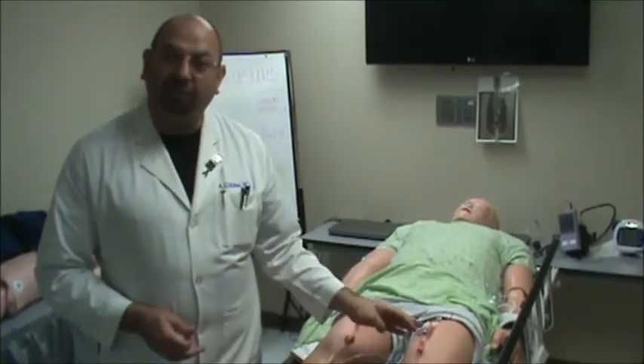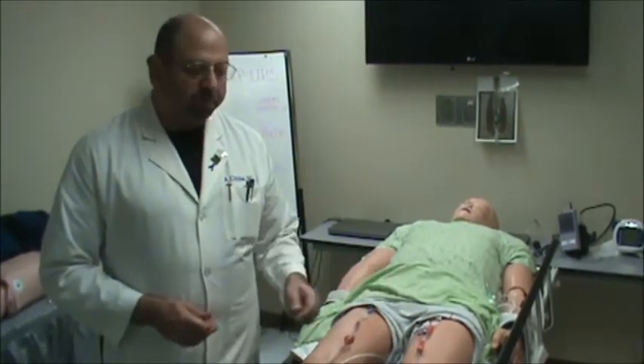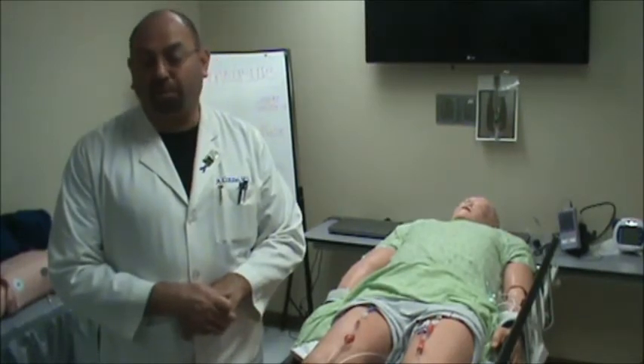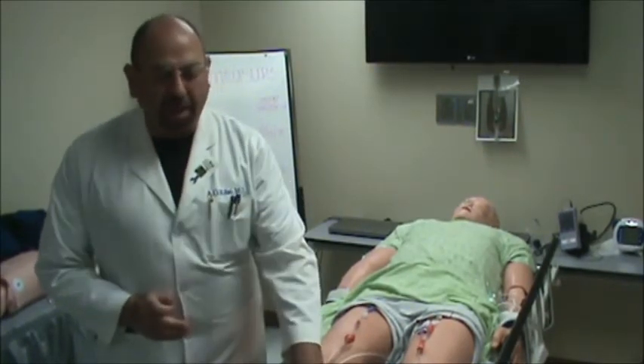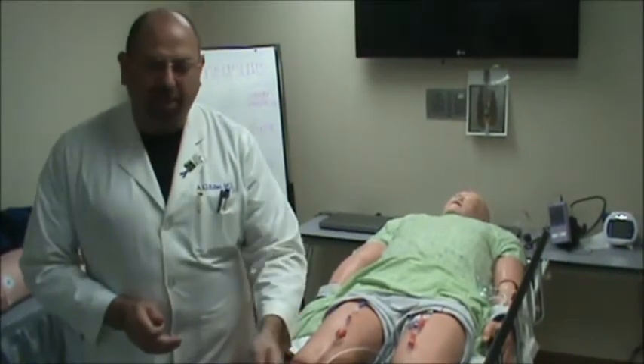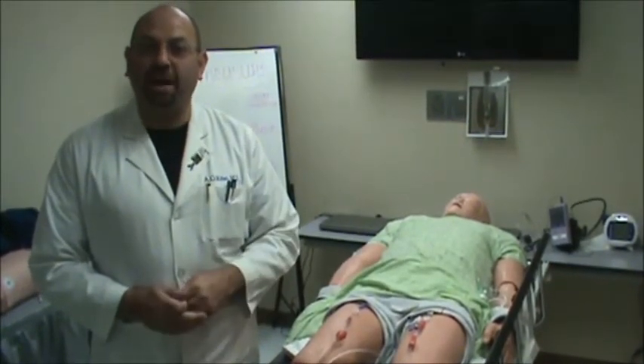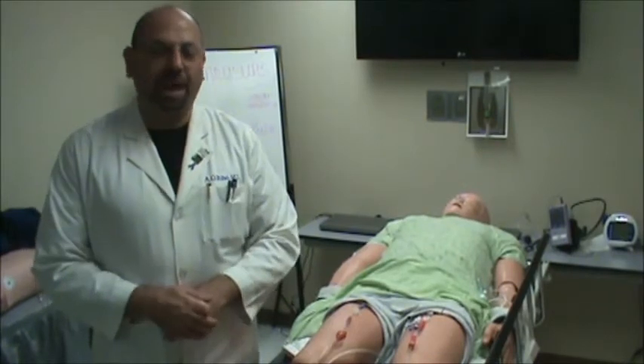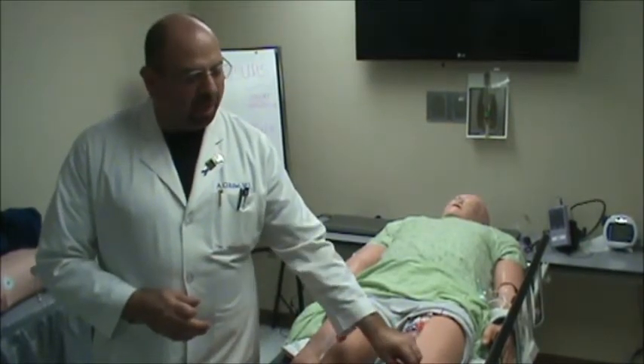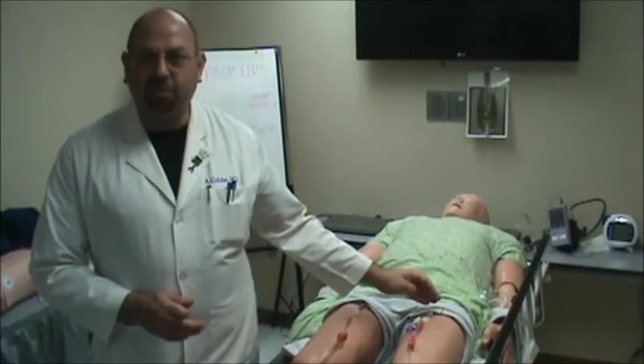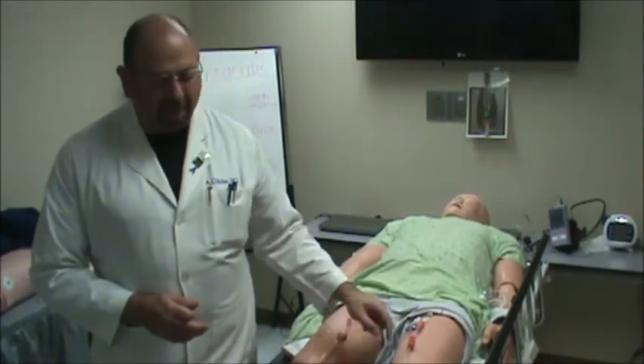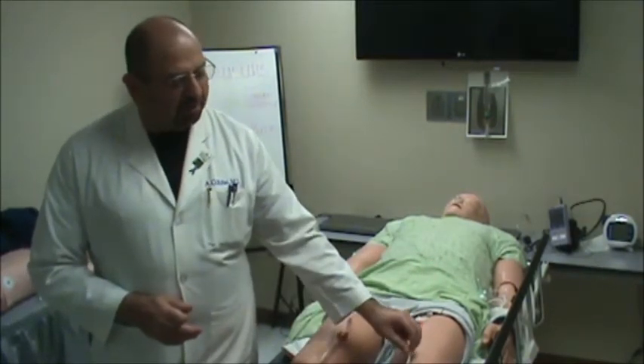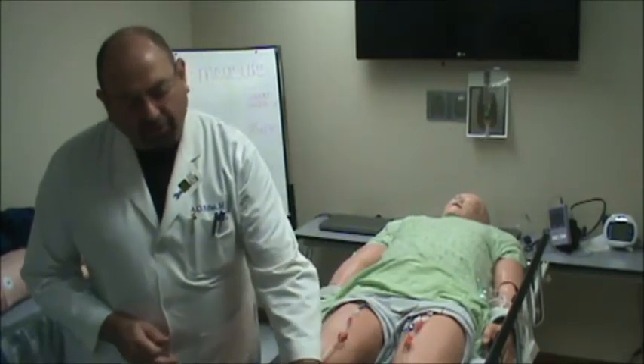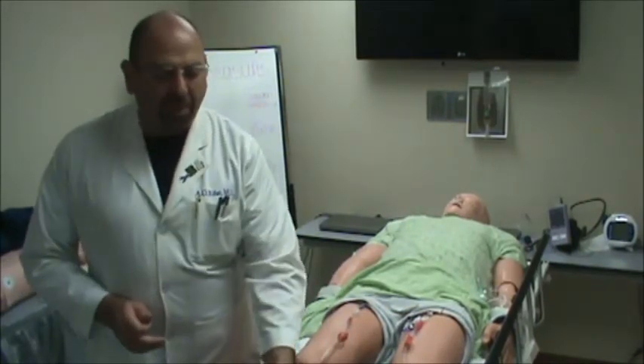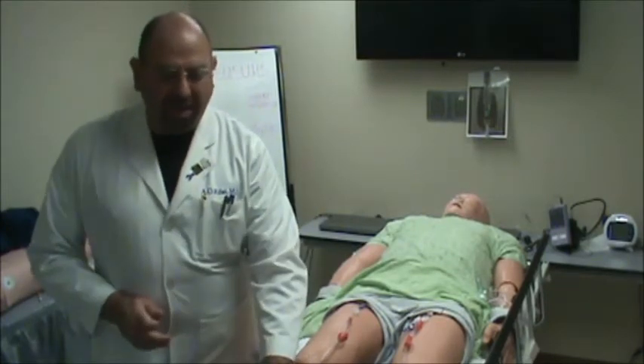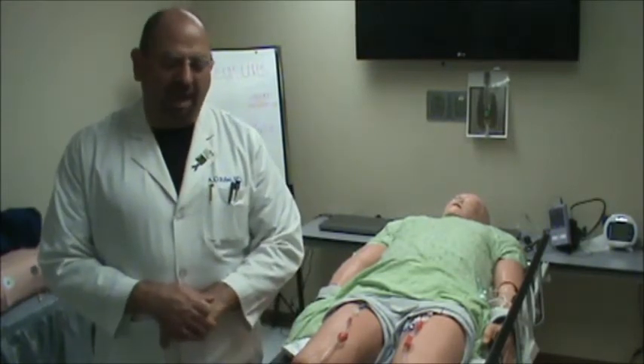So we may have to catch up with IV fluids, what we call replacement fluids. Keep in mind, if the blood pressure drops, then the filtrate will be lower. If the blood pressure is higher, then the filtration will be higher. If there's a kink or an elevation in the venous pressure, like the catheter is clogged or kinked, then you have a lot of resistance in the venous circuit, so the filtration will be even higher. Sometimes if the filtration is a lot lower, you may have actual clotting inside the catheter.